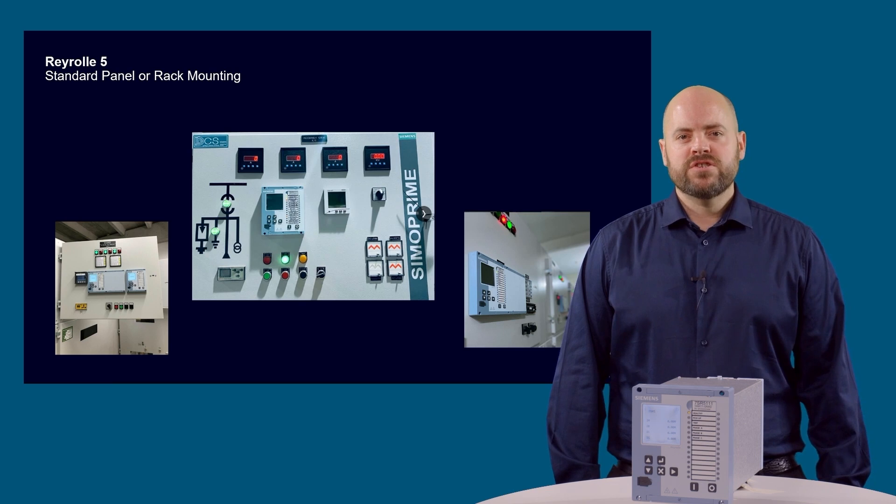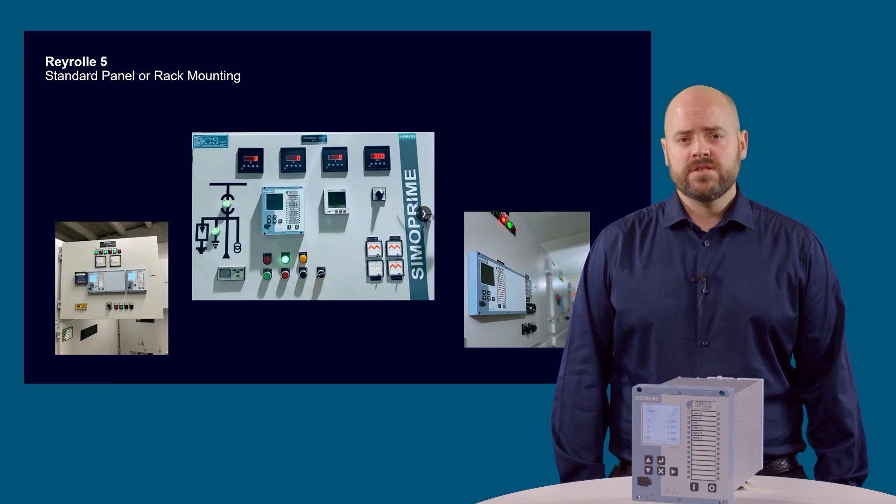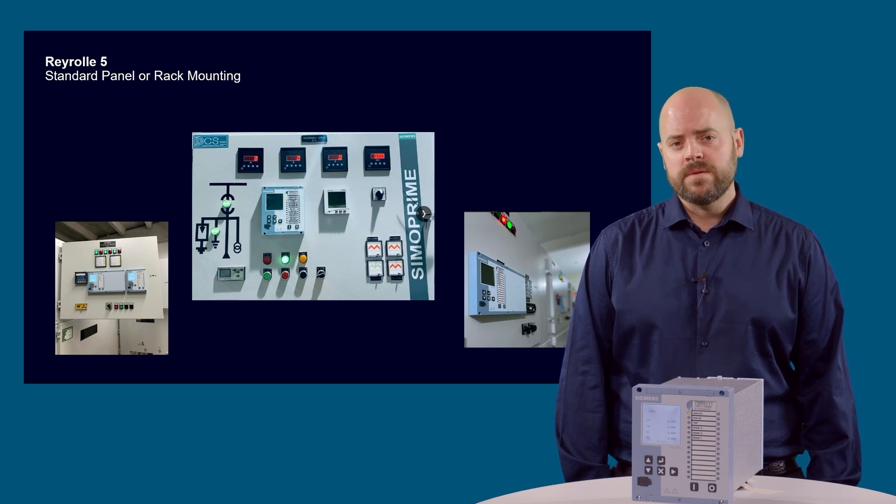The Reyrolle 5 protection devices are available in 3 case widths suitable for panel or rack mounting. The case size is determined by the number of inputs and outputs required, with a maximum of 39 binary inputs and 20 binary outputs. Optional inputs and outputs include 3 arc flash detector inputs, 3 high speed binary outputs and up to 16 temperature sensor inputs.